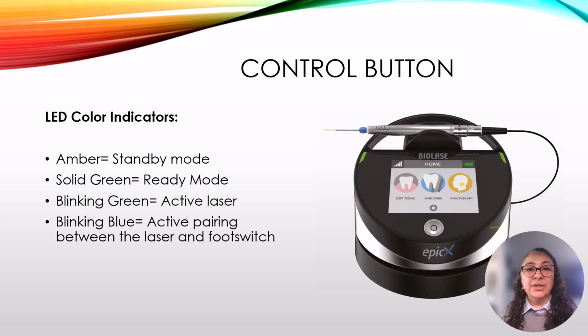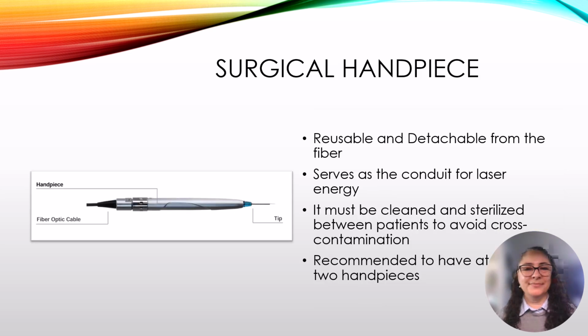The LED color indicators show the current status of the laser. Amber indicates a standby mode, solid green indicates a ready mode, a blinking green light indicates the laser is firing, a blinking blue light indicates the active pairing or syncing between the laser and the foot switch. If you are unable to distinguish the colors, make sure you read the display, as the color indicators will also show in text form what mode it is in.